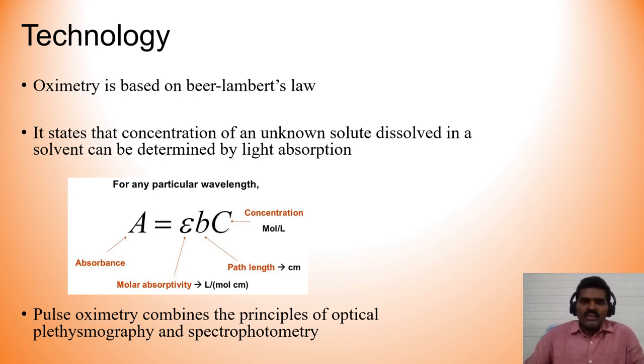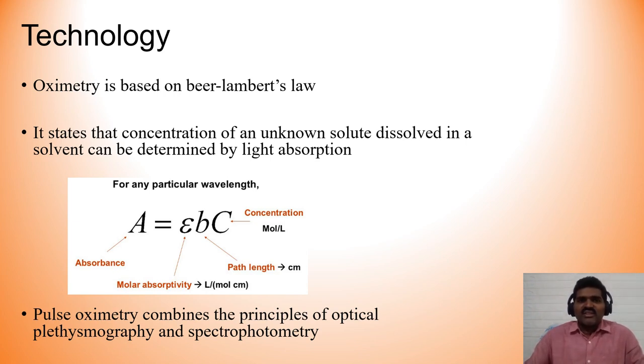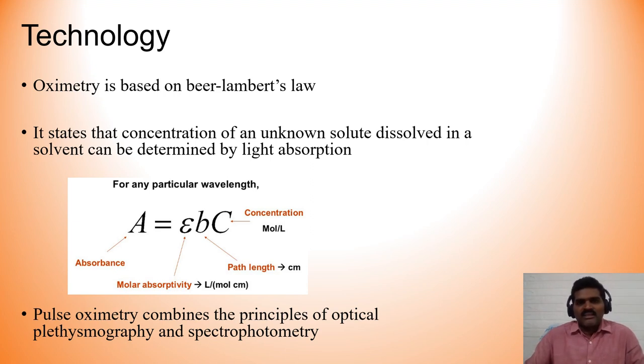Regarding the technology used in recording pulse oximetry: oximetry is based on Beer-Lambert's Law, which states that the concentration of an unknown solute dissolved in a solvent can be determined by the characteristics of its light absorption. This is given by the equation: for any particular wavelength, absorbance (A) equals molar absorptivity (ε, a constant given in liters per mole-centimeter) multiplied by the path length (b, in centimeters) — the distance light must traverse — multiplied by the concentration of the substance in moles per liter.